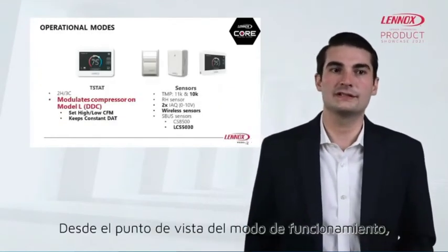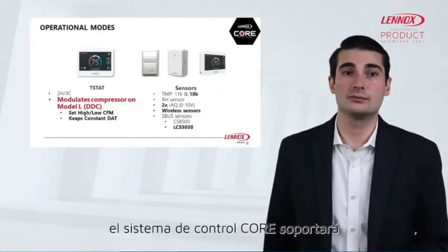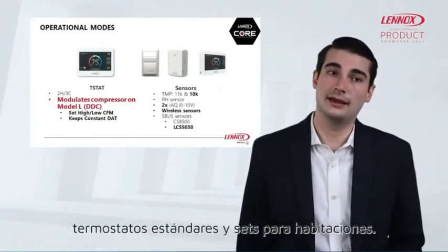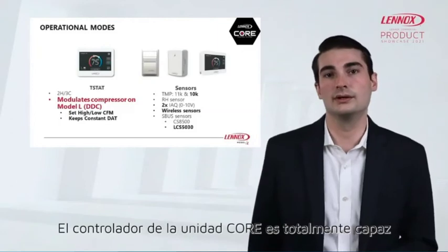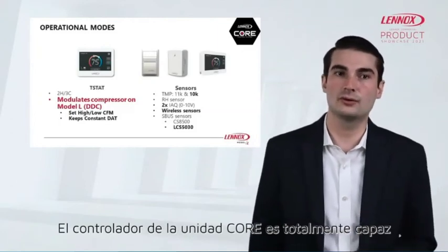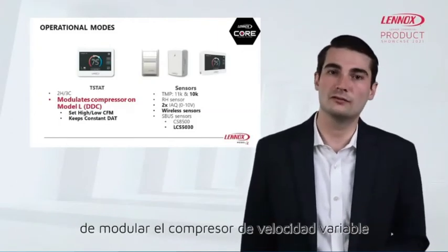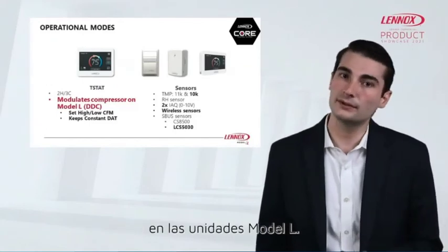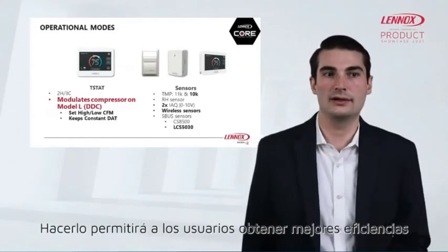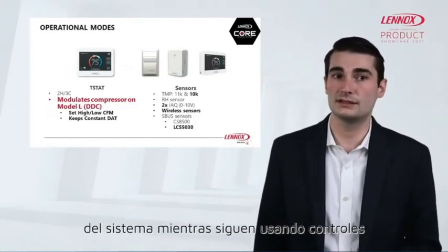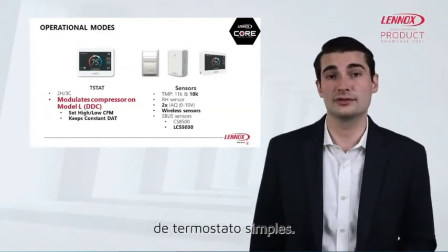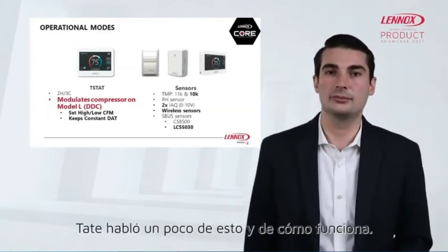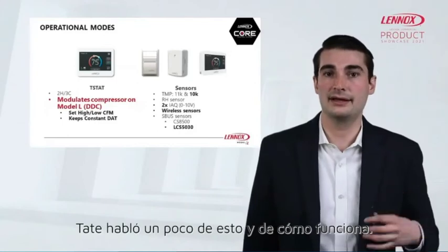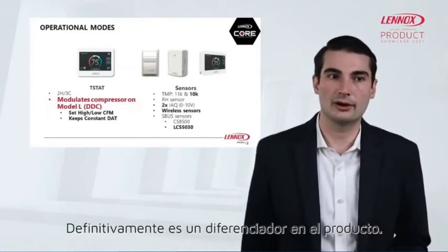From a mode of operation standpoint, the CORE control system will support standard thermostat and room sensor modes. When using thermostats, the CORE unit controller is fully capable of modulating the variable speed compressor on Model L units. Doing so will allow for users to get better system efficiencies while still using simple thermostat controls. Tate laid a little bit of that out and how that works. It's definitely a differentiator in the product.